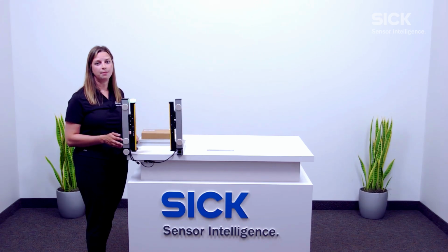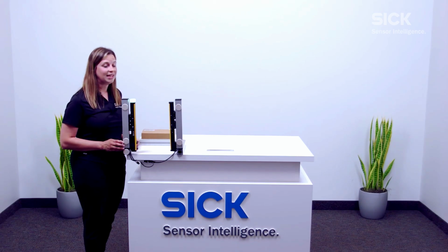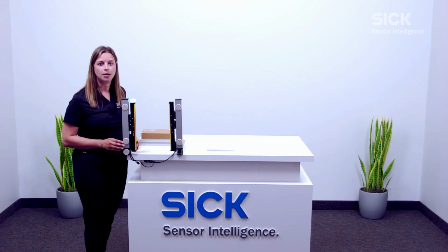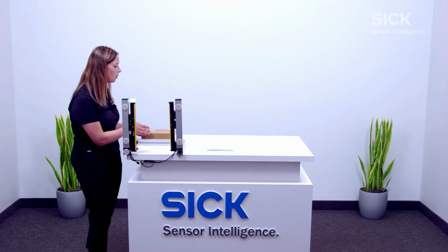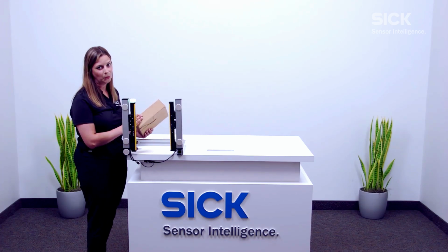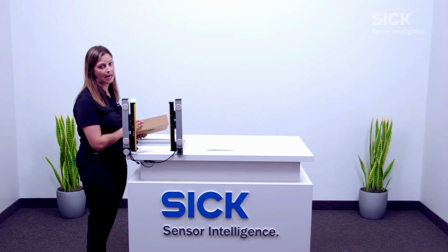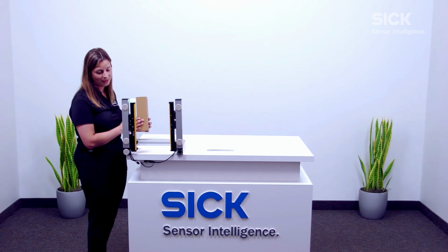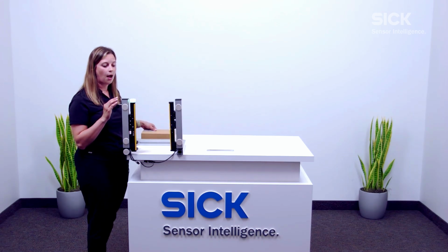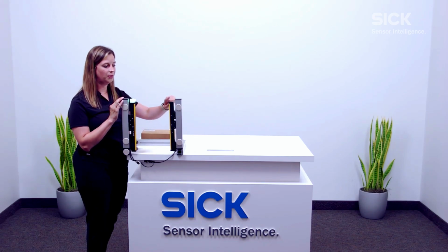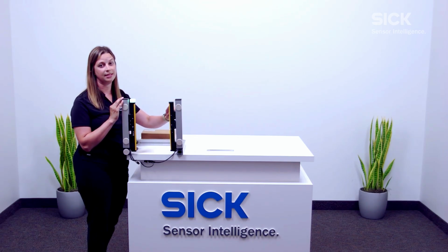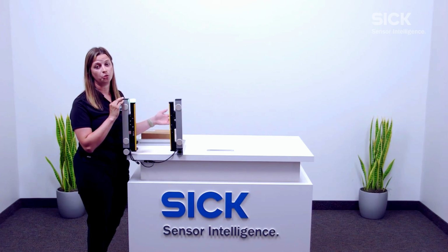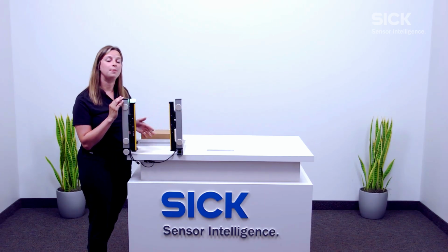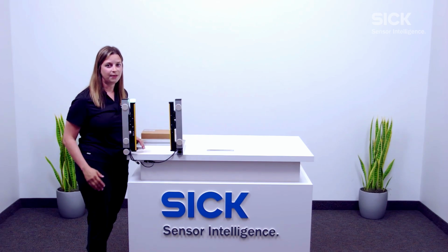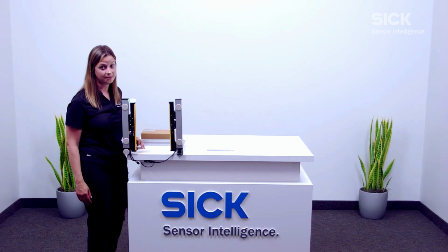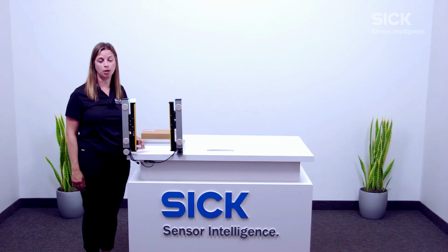With this, there are some limitations of the technology. You will need to use a light curtain with a 14mm resolution. There is also a minimum height of an object, which you surely won't encounter in the tire industry, of 134mm. We also cannot block the entire protective field height, so we'll need to have at least the top two beams remain active throughout the entire object passing through. This again is a feature that you can program using our dip switches on our System Plug 2.